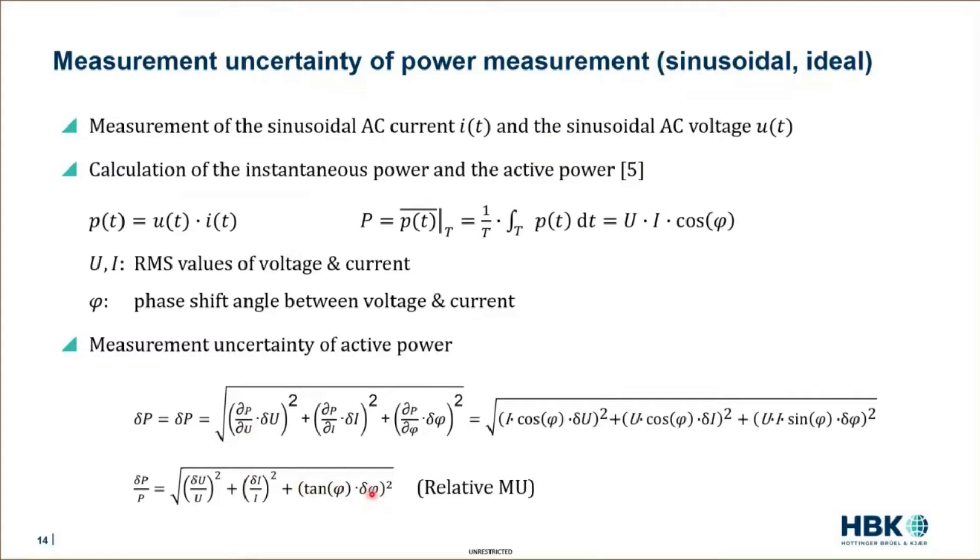It's useful to do this in the first step. Because if you think about electric drive applications, the electric machine represents a high inductive load. Therefore, the currents are more or less sinusoidal as we saw in the measurements before. And for this reason, most of the active power is transferred in the fundamental. If you know the measurement uncertainty of the fundamental, that's a good estimate to guess how big the overall measurement uncertainty of the total power could be. But of course, if you want to go into detail, we need something different.